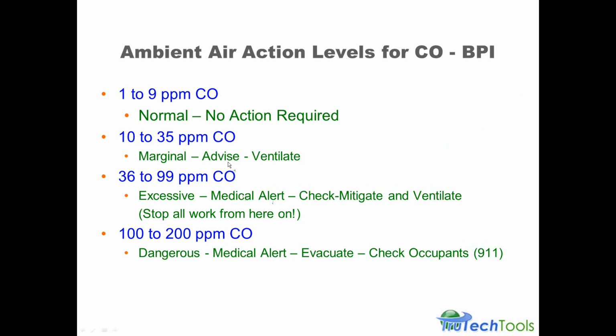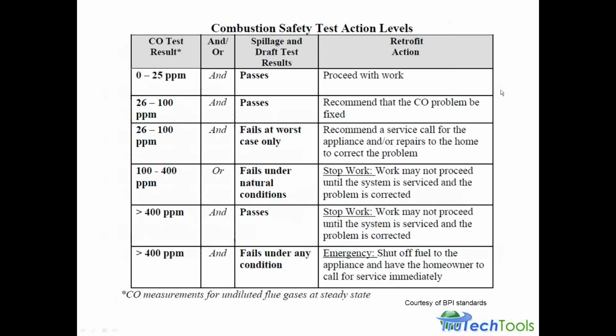We do have some personal CO monitors that we sell at TruTech. We have them set to go off with the first alarm at 35 parts per million and the second alarm at 100 for these very reasons, because these are very reasonable and appropriate action levels.